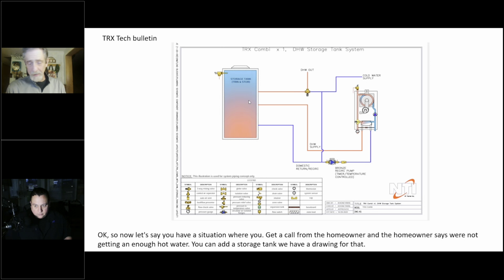That's usually the best cost-effective alternative, and I hate to talk people out of buying the Trinity tank, but honestly, the best cost-effective alternative is just an electric water heater. Sometimes it doesn't even have to be a big electric water heater. Depending, you just need to have a pump that's going to create flow, and that's right here. That's your pump right there. And it has to be a bronze or a stainless circulator because it's potable water at this point.